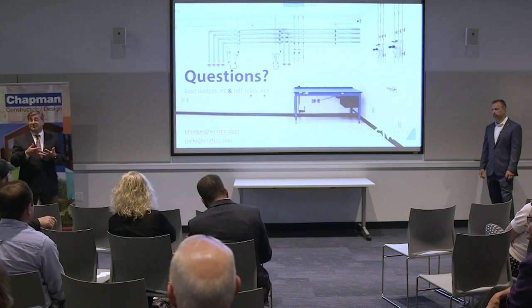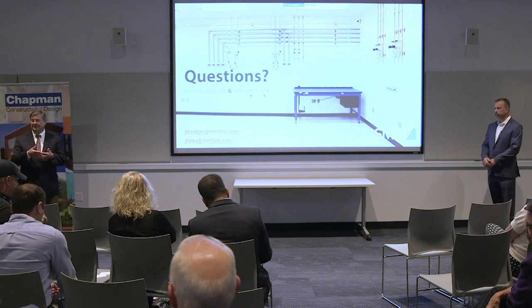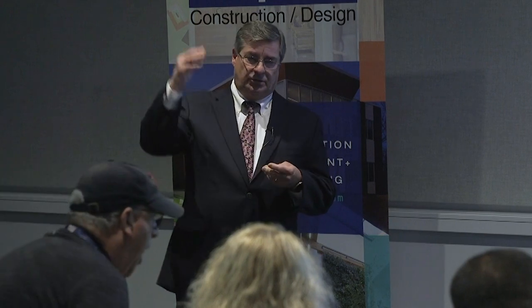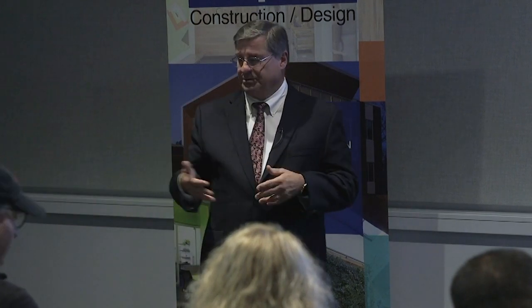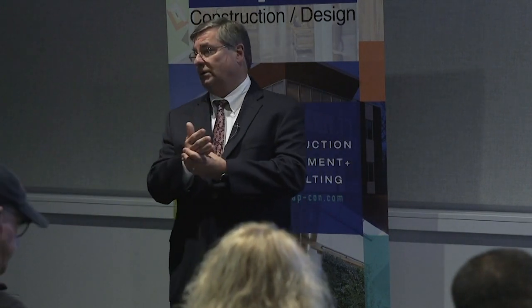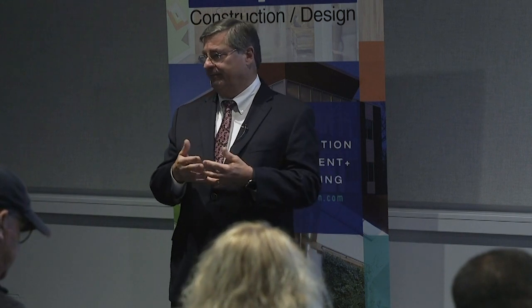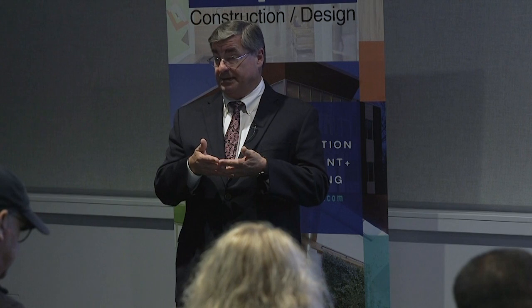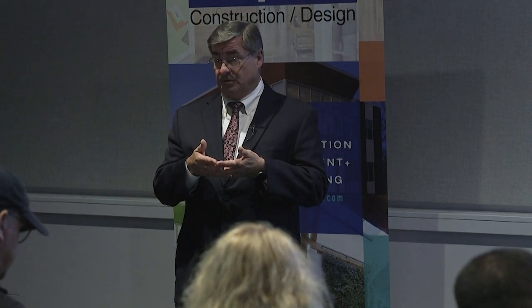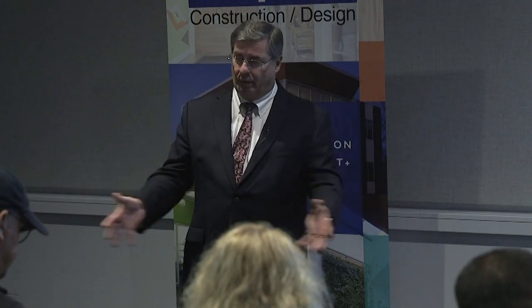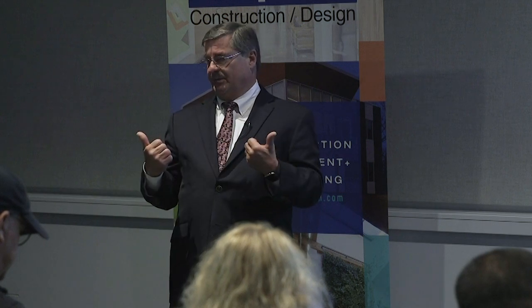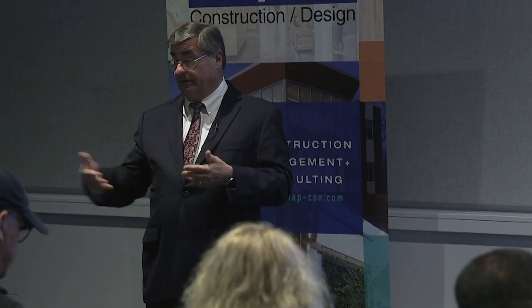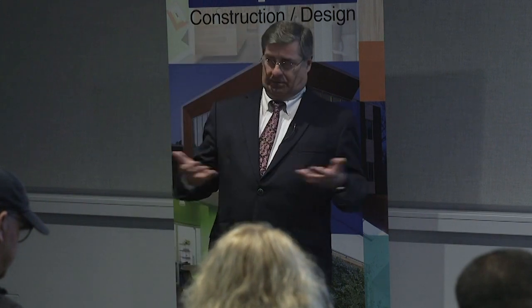From a containment standpoint, the biological containment, if you're doing a BSL-3 facility, for instance, you would normally, perhaps the lowest grade would be an epoxy paint over drywall, and that would be the level of integration. Containment in BSL-3 is done via directional airflow. All air is going into the space and not escaping. So if you have little fissures, it's okay. You have little leaks, and you want a leak under the door in order to maintain that containment.